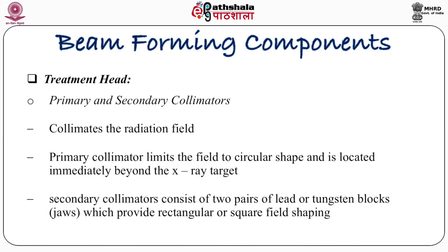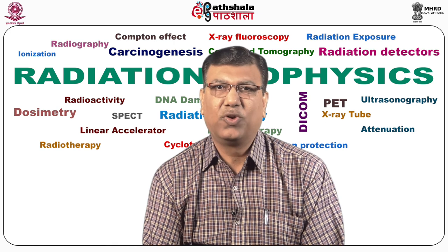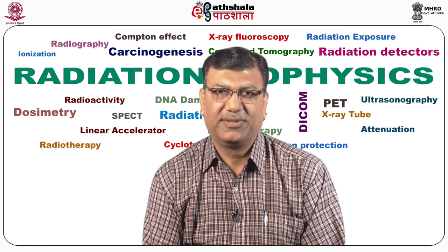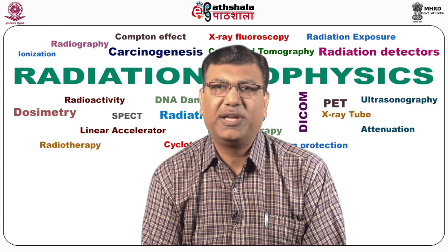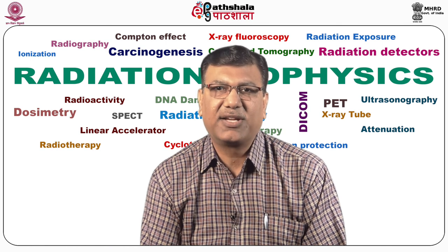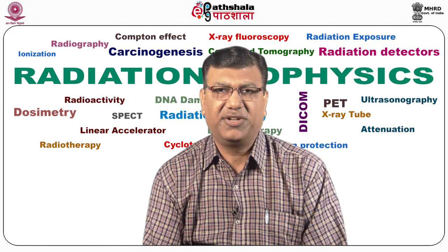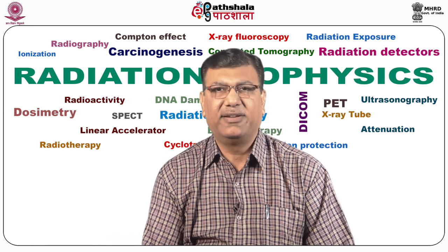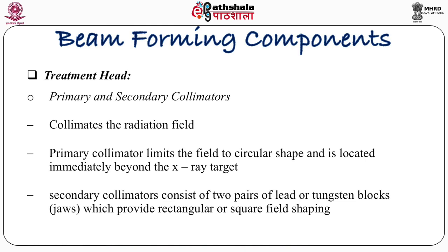The treatment head has primary and secondary collimators which collimate the radiation field. The primary collimator limits the field to a circular shape and is located immediately beyond the X-ray target. Secondary collimators consist of two pairs of lead or tungsten blocks — also called jaws — which provide rectangular or square field shaping. Most of the treatment marking done on the patient surface is either rectangular or square, so we have to change the field from circular to square shape, and that is why secondary collimators are used in the treatment head.